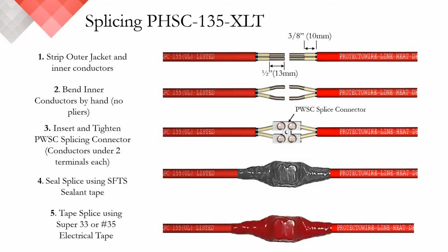Earlier, we discussed the PHSC 135 XLT detector. This is our standard detector and is a universally compatible, normally open resistive contact device. If or when you're required to splice this detector, the process for splicing is quite simple, as you can see here. The first step is to remove a small portion of the outer jacket and heat-sensitive polymers. With the metal conductors exposed, you can bend them gently and slide them into a Euro-style compression terminal, or our PWSC. You must always use compression terminals with all Protectowire detectors.